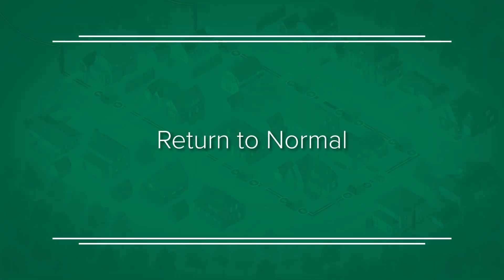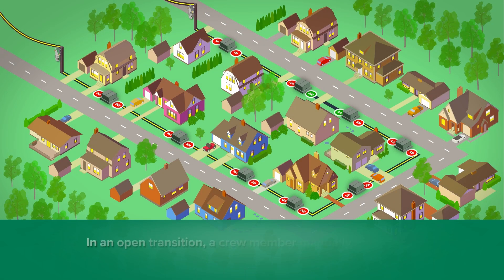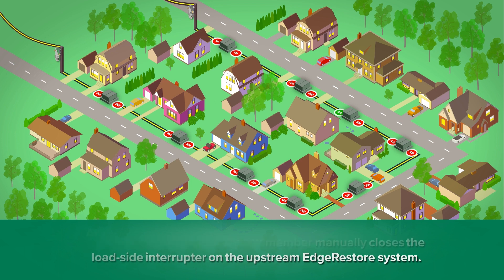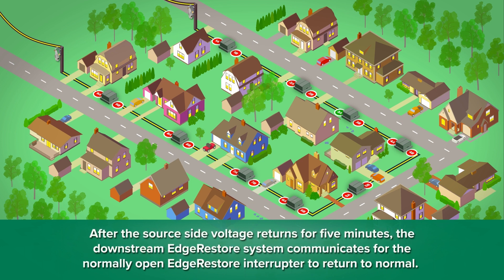After a crew repairs the cable fault, the return-to-normal process can begin. In an open transition, a crew member manually closes the load-side interrupter on the upstream Edge Restore system. After the source-side voltage returns for 5 minutes, the downstream Edge Restore system communicates for the normally open Edge Restore interrupter to return to normal.